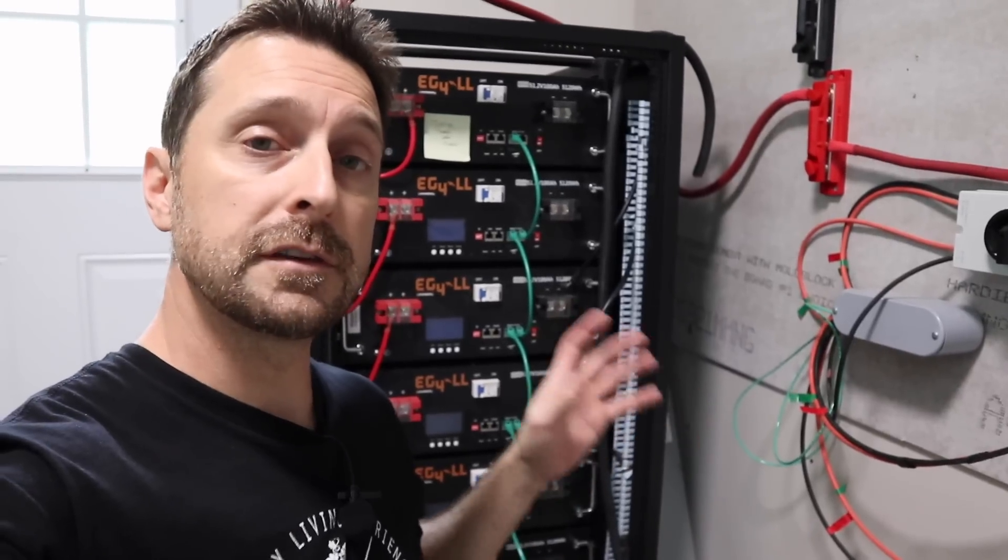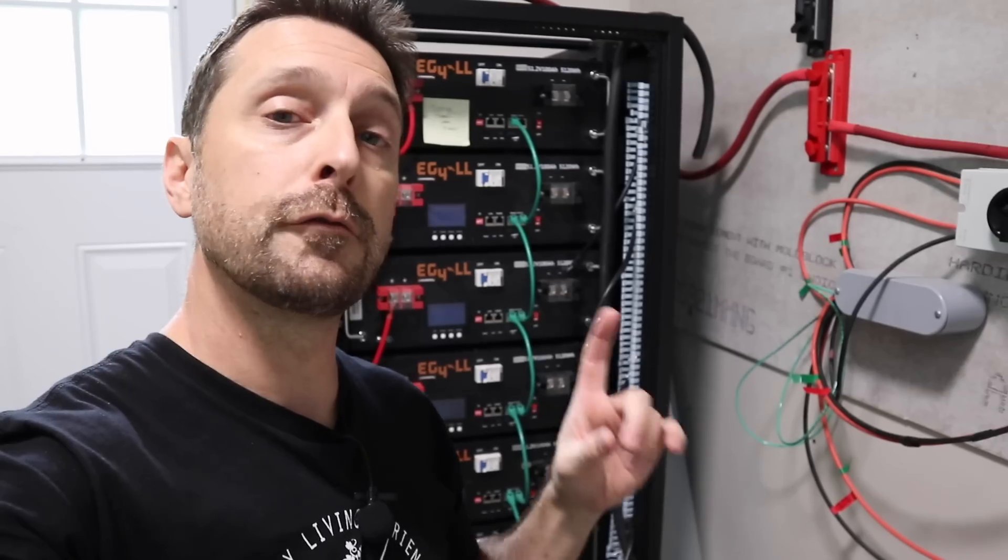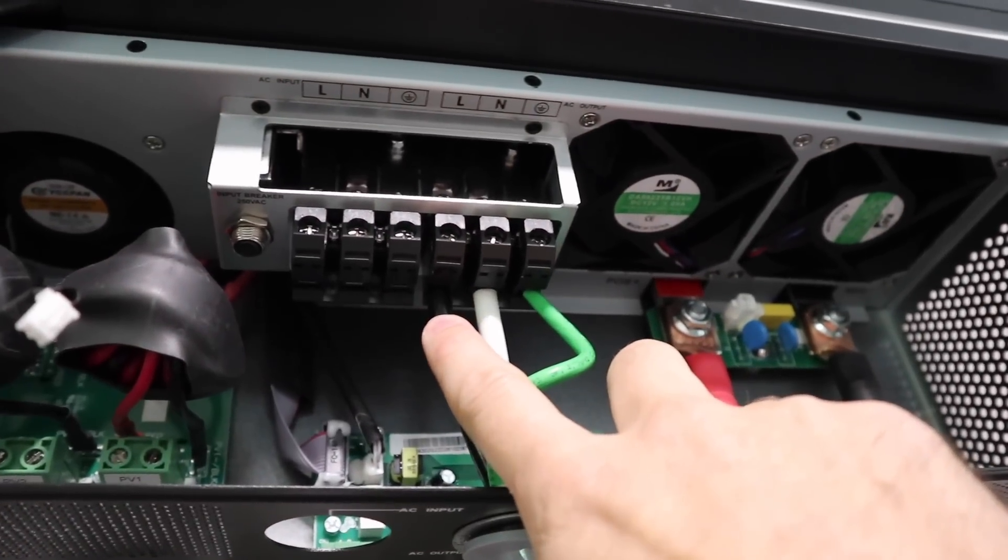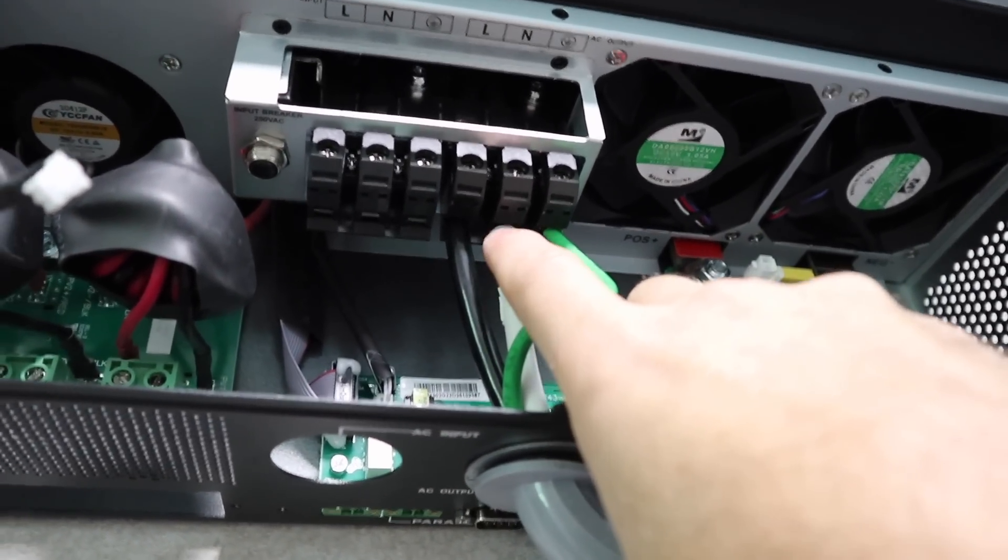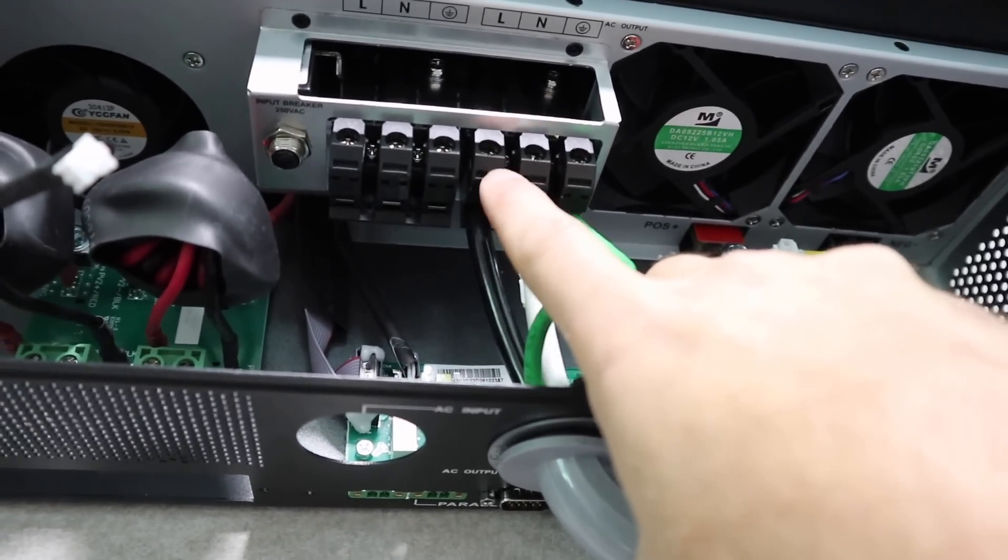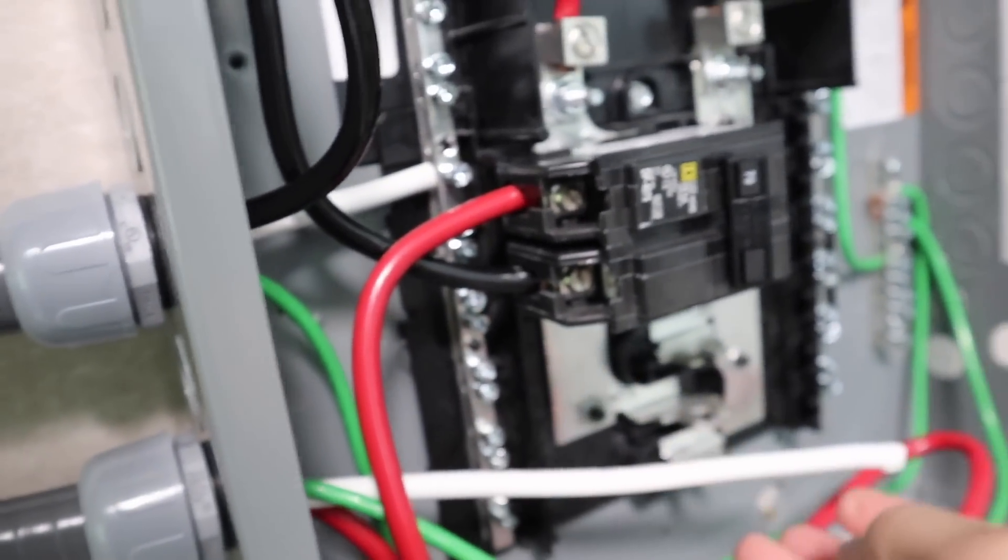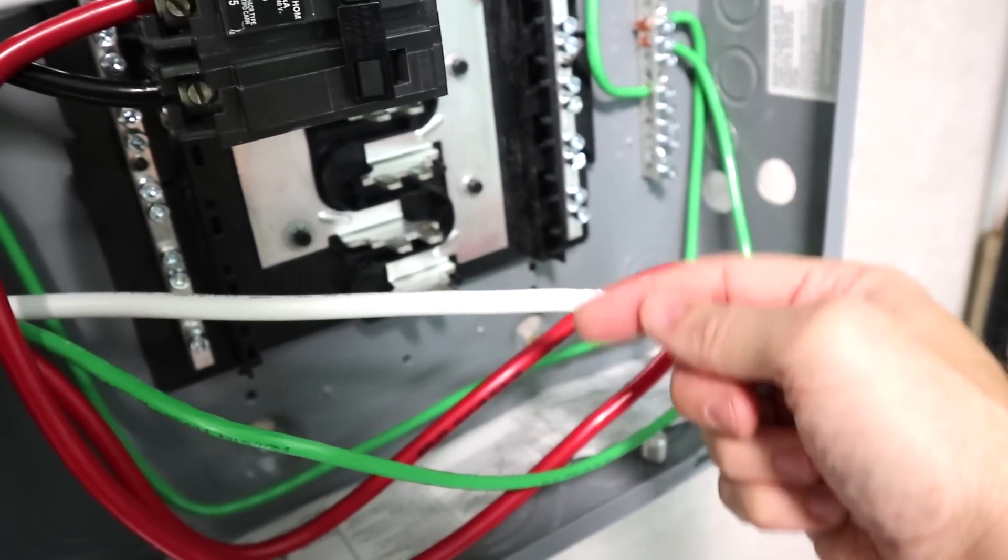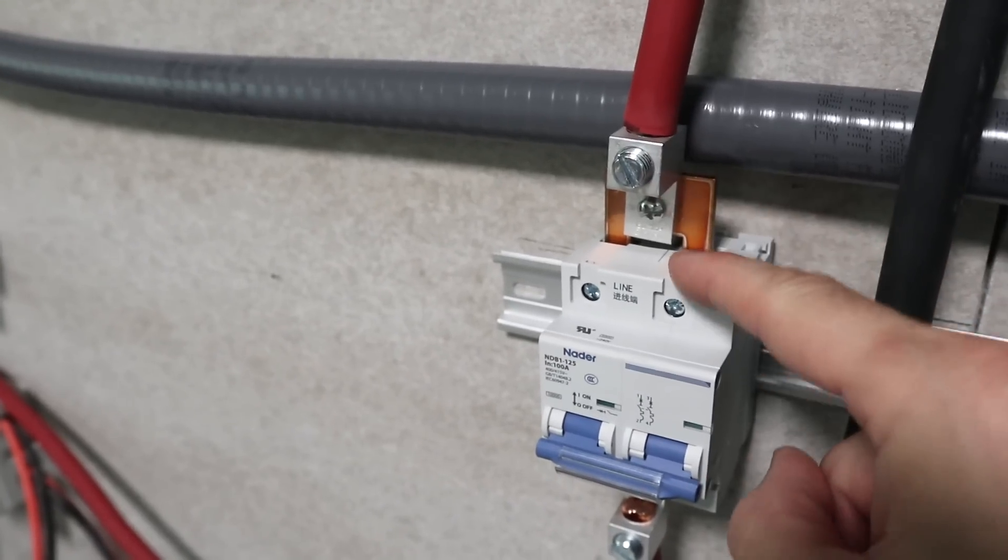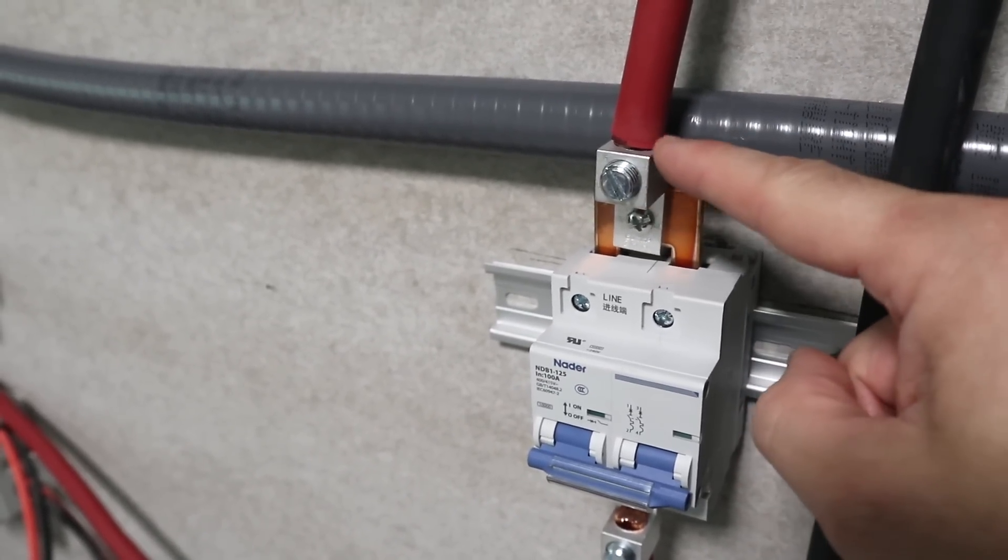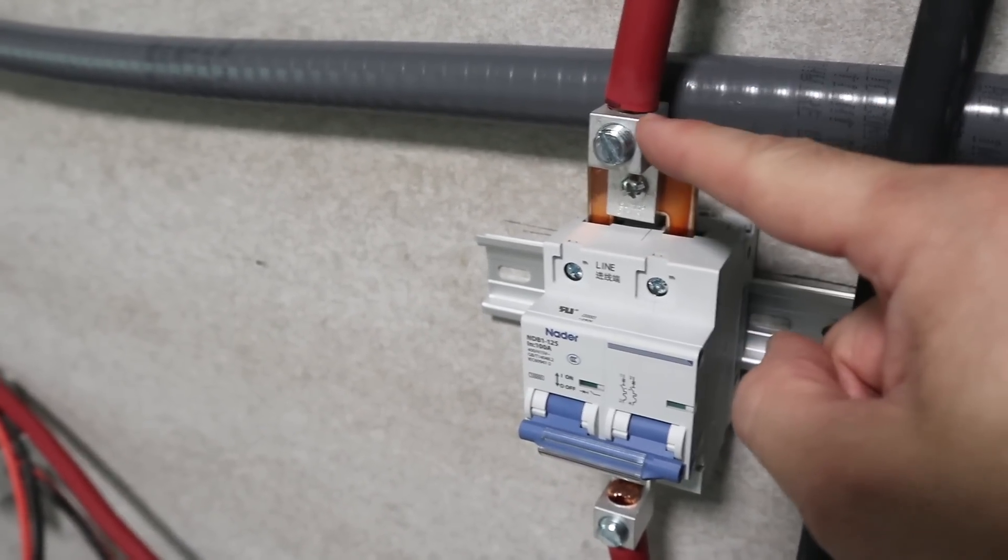I'm not going to go over again with this build how to connect these batteries all together. I did that in the video linked at the top of the screen. For this first inverter that I connected, we have our hot, our line, our neutral and our ground. These are extremely tight with the four gauge wire. If there's any deviation in the shape of the end of that wire, it's extremely difficult to get them into these terminals. That is the same case with this Square D panel. What I found is to leave the insulation on until you are absolutely ready to perfectly push it through one of these holes.